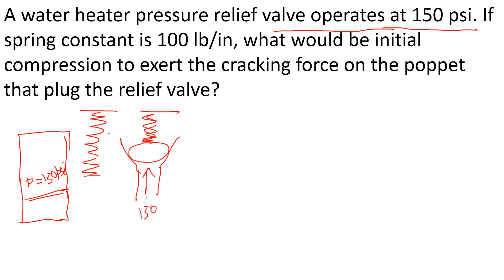The flow is coming this way at 150 psi. That is the initial compression of this spring, so that will exert some force downwards to balance this pressure coming upwards. Now, to make full flow, if you just balance the force by 150 psi, it's not going to make full flow.